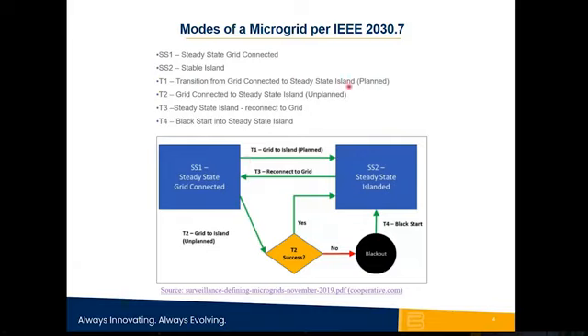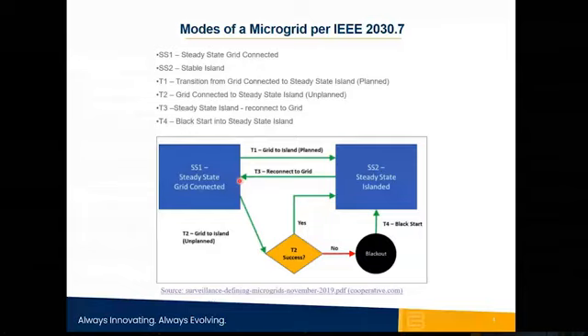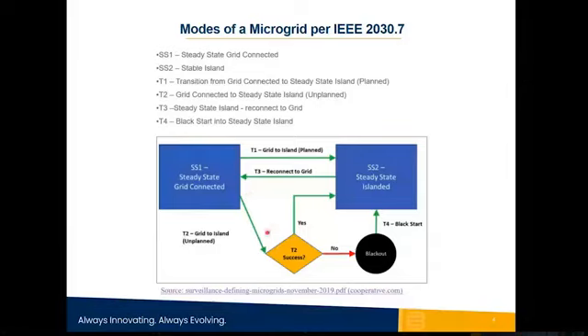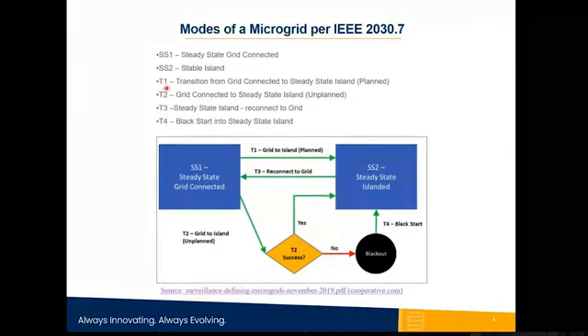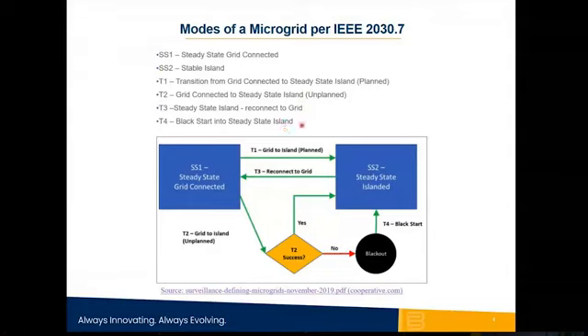But you can also have unplanned grid connected to steady state transitions. For example, a forced outage. Now, when you have a forced outage, let's say a tree falls on a feeder and now that feeder is not available to supply power, then the local generators on site need to supply that power. If the transition is successful, then we have T2, which is grid connected to steady state, unplanned. And an example of that would be standby generators following NFPA 110, where they start to come online to supply the critical loads within 10 seconds.